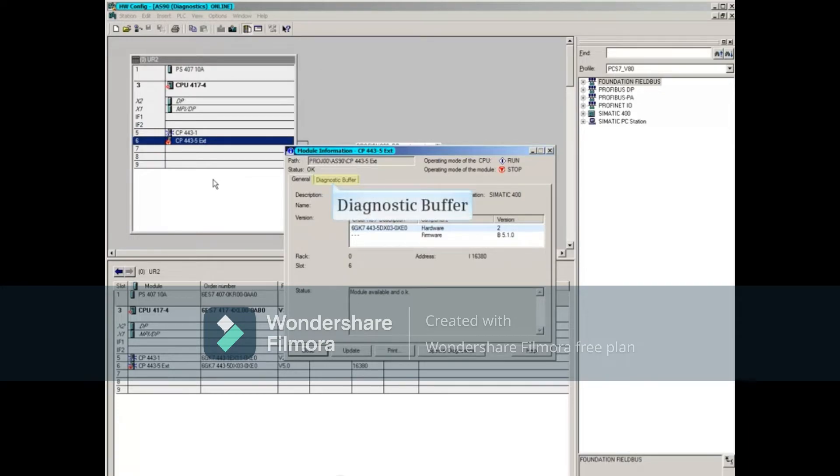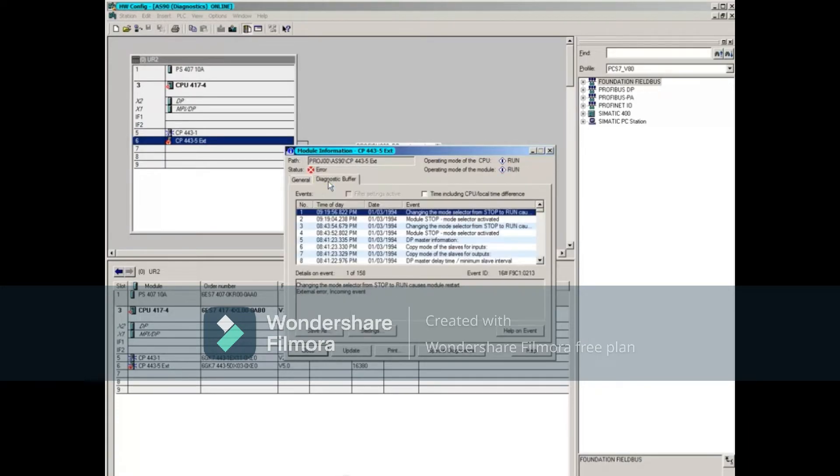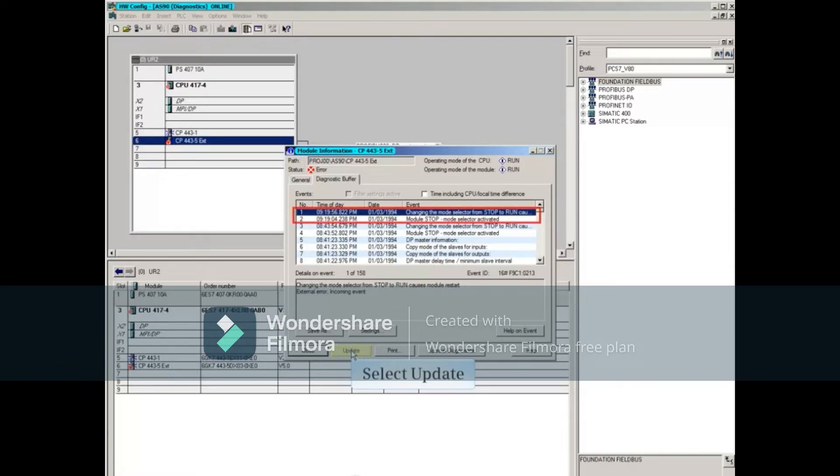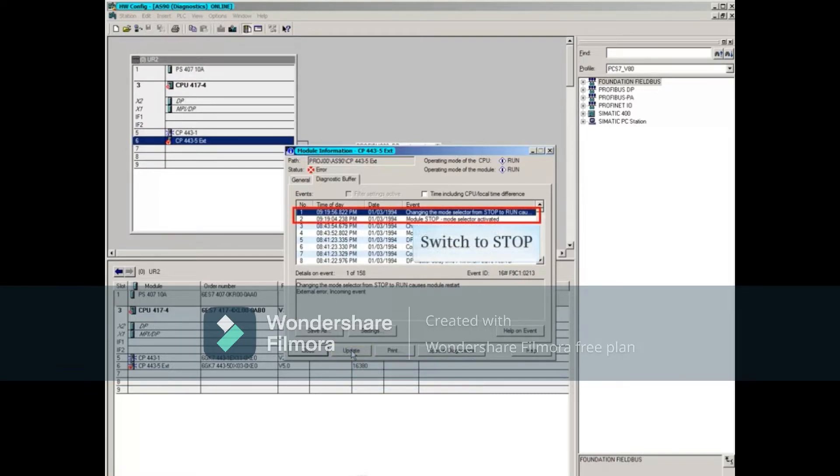Select the Diagnostic Buffer, and click the Update button. The buffer should show the two events, putting the switch in Stop, and then in Run.